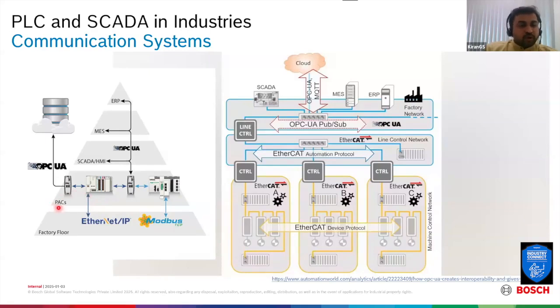Sometimes called programmable automation controllers. Yeah, this is what it is. But basically, when we are connecting the low level devices, we generally have a lot of communication protocols like Ethernet IP, Modbus, and even OPCs are available. Above this, when we are connecting the PLCs to the SCADA systems or the next level MES system, typically OPC UA is a standard communication protocol.